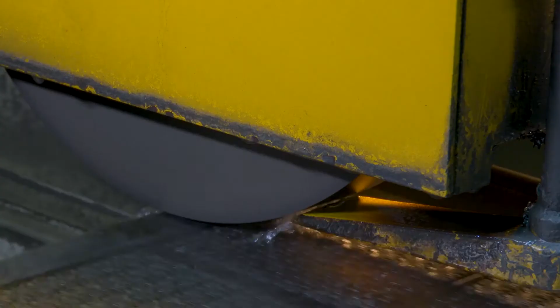Now we are standing inside the grinding room for the magnetic relay workshop. The magnetic relay is the heart of the RCCB. All the manufacturing process of the magnetic relay is precisely controlled within micron levels, so that we get consistent residual tripping output once installed inside the RCCB. The first step starts from grinding the tripping lever. In the video I will show how we do the process one by one.